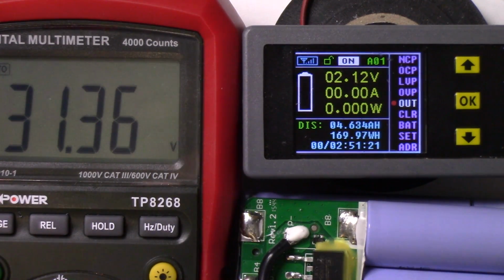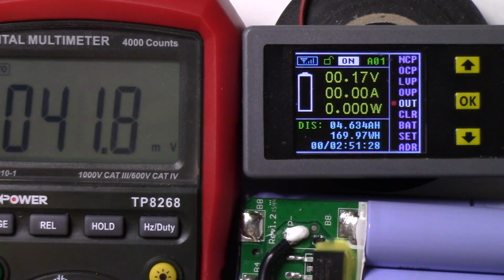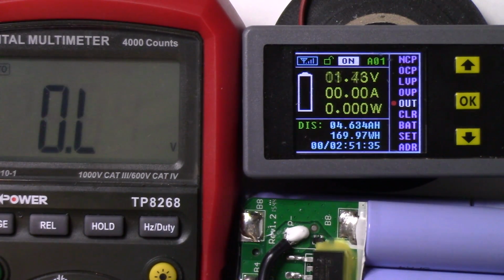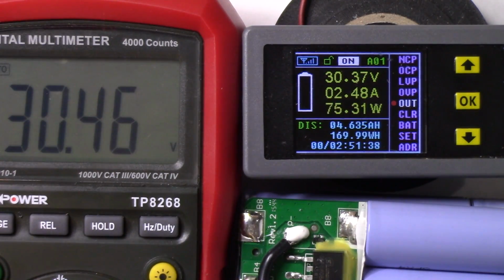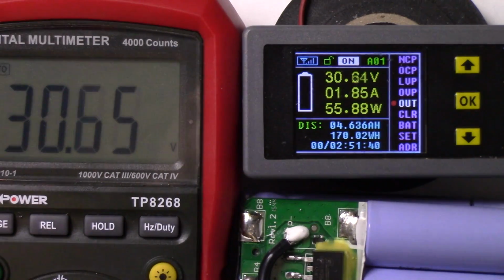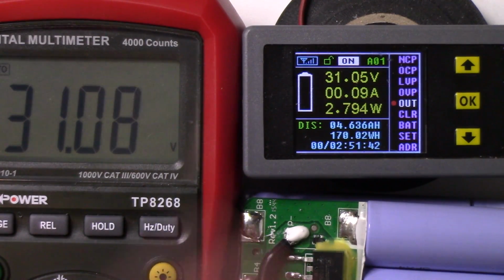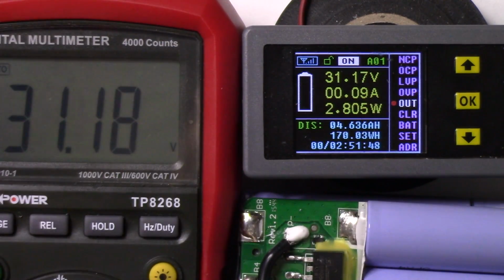Oh yeah, let me show you the reset here. I'm going to take the pigtail off the meter, and you see it goes to zero, as it should. A slight charge there, it's going down, and put it back together again, and you can see the charge circuit starts all over again. So again, 31.05 here, or 12, perfect, right? That's how you reset the over discharge protection—just disconnect the circuit from the battery, reconnect it, and boom.